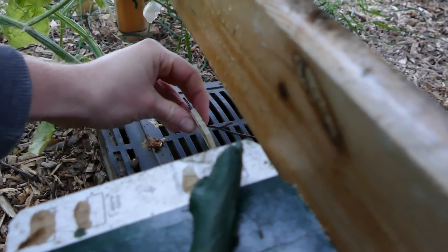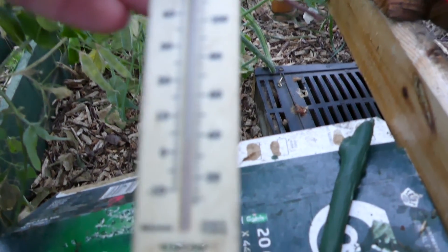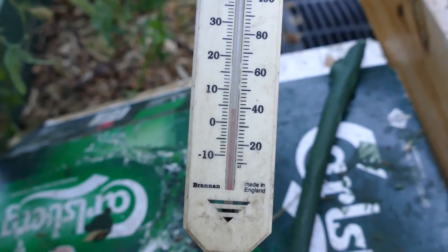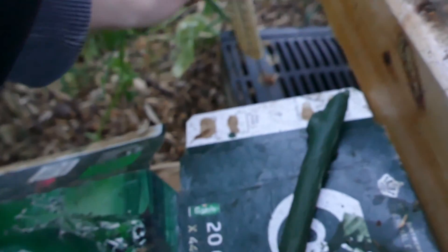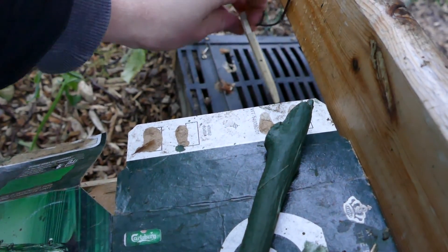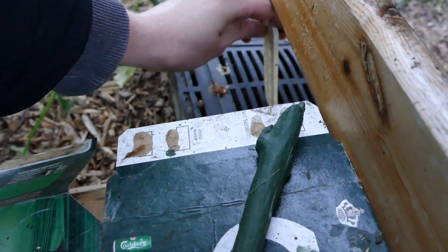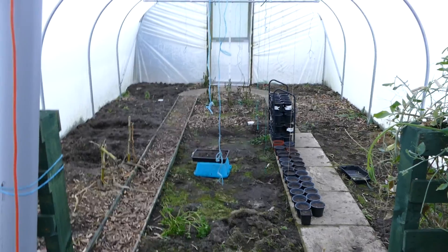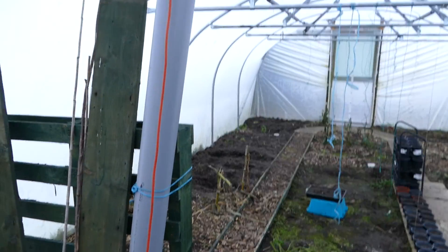I'm pretty sure it's going to be close to freezing at the moment because it hasn't been very warm recently. Oh actually it's quite good — about five degrees there, so that's quite impressive. Five degrees on the outlet temperature. So there's still a decent amount of heat stored in the tank and underground, which is good. I checked it earlier when it was really cold and it was closer to two or three degrees, but it must have warmed up a little bit since the minus eight and it's now five degrees on the outlet.